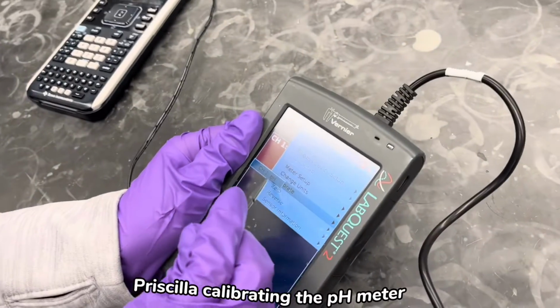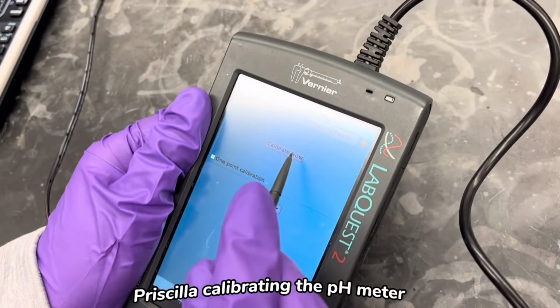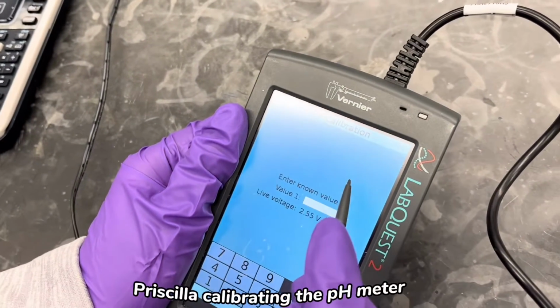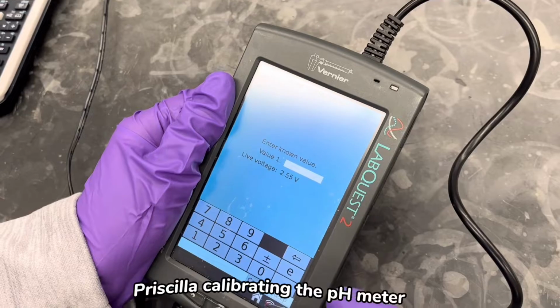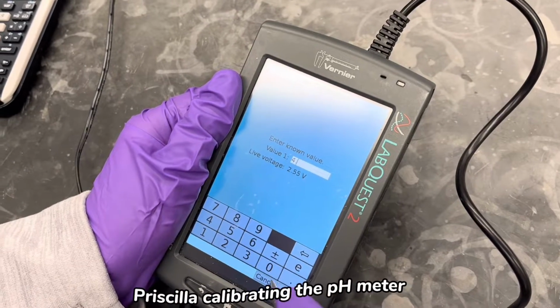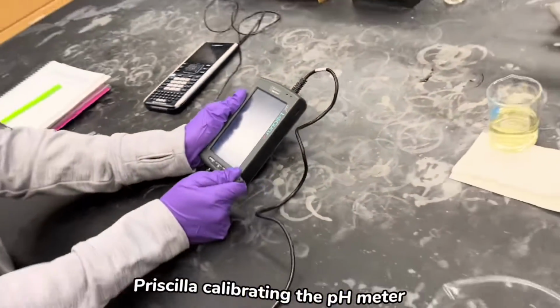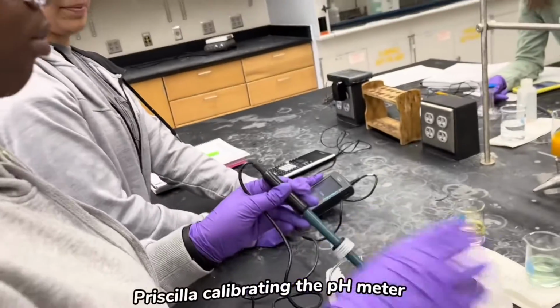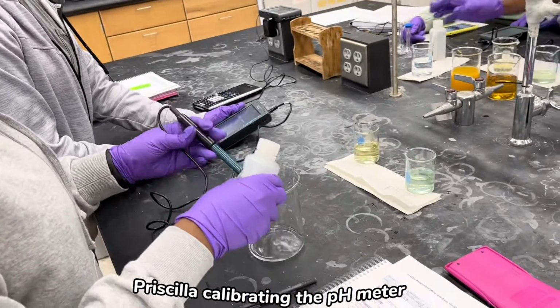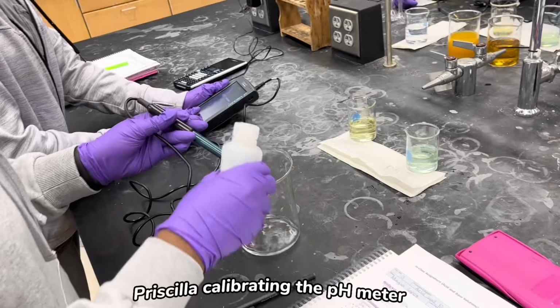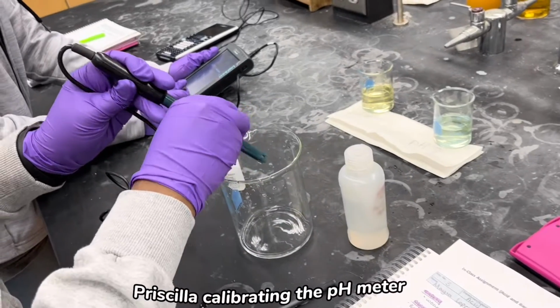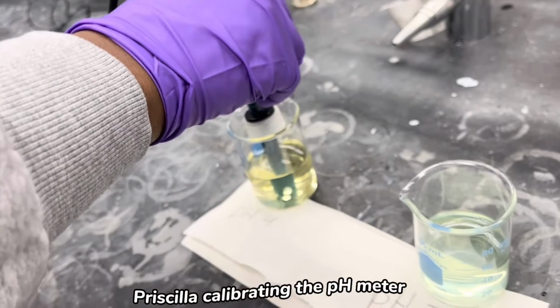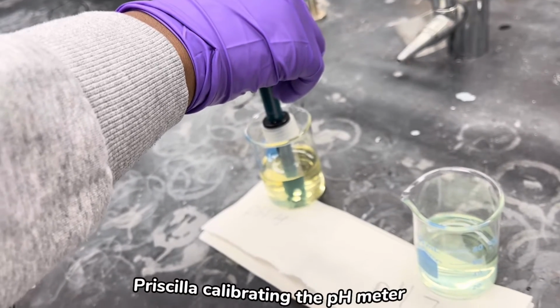First, we're going to calibrate the pH meter by using buffer 4 and 7. We start off by removing the pH probe from its container and rinsing it off with distilled water. Then we place it in buffer 4. We go back to the pH meter and under Files we click Sensor, and it will lead us to a new page where we press Calibrate Now. Until it reaches a stable voltage, we enter the pH of 4.